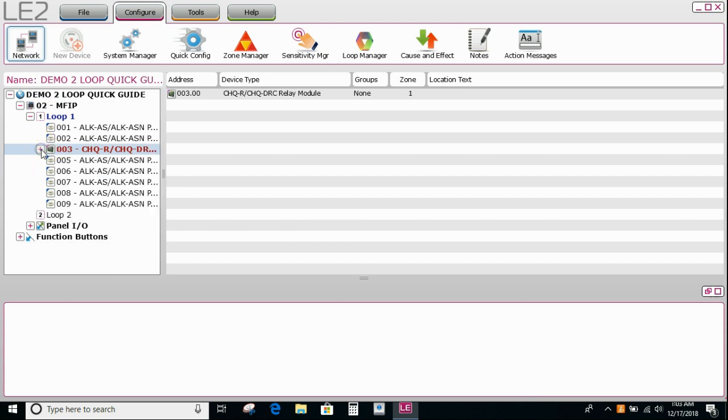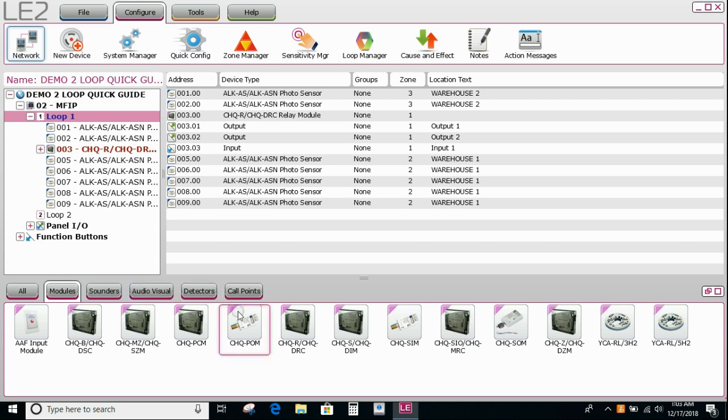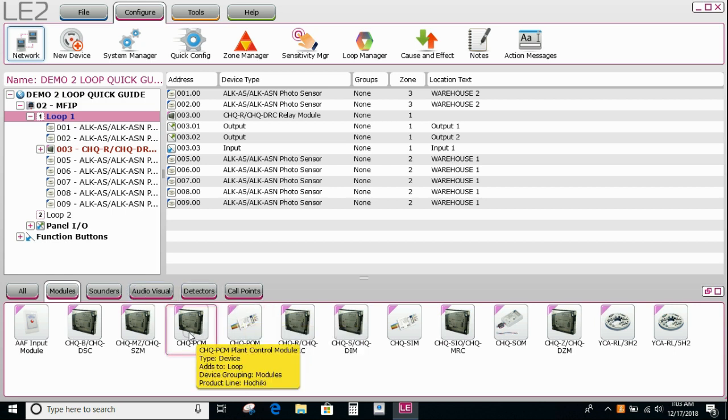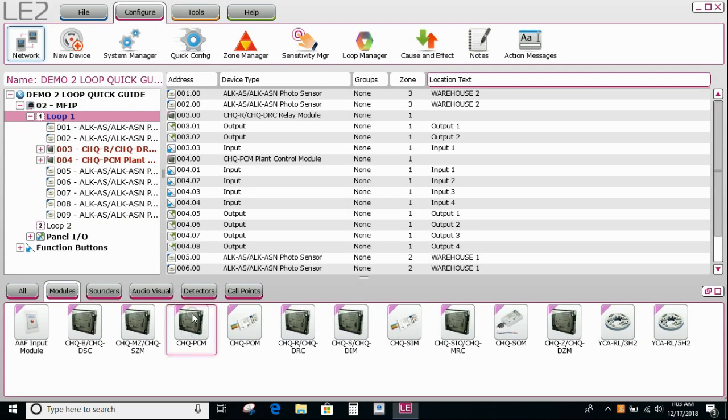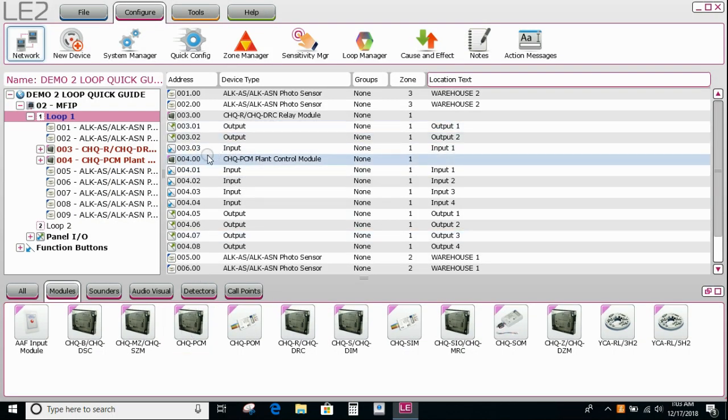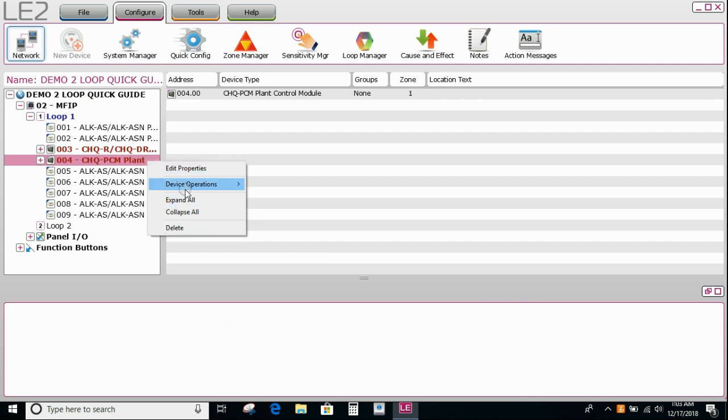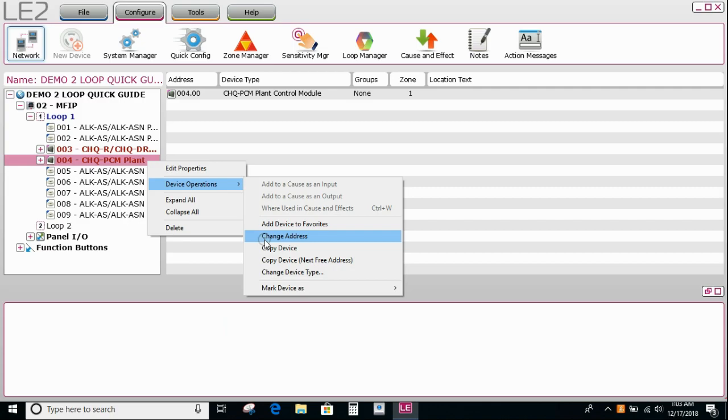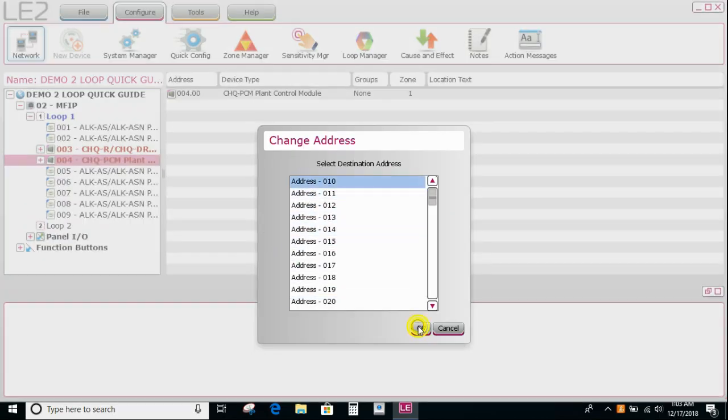Now we may also have some inputs coming back from, let's say, valve monitor and a flow switch. Let's add a PCM by double clicking. It gets added to the next available address. If I ever need to change any of these because it's the wrong address, I can right click, go down to device operations, and then change address. And in there I can select the address that it's now going to be. And there it is, address 10.